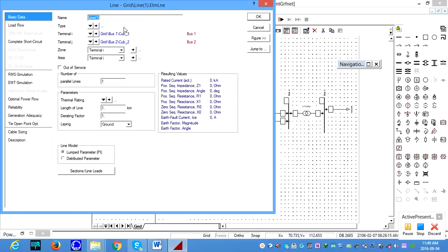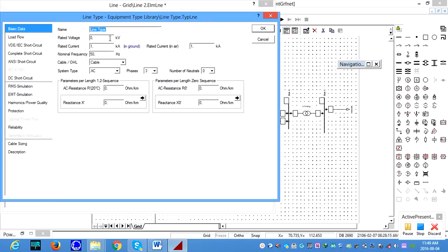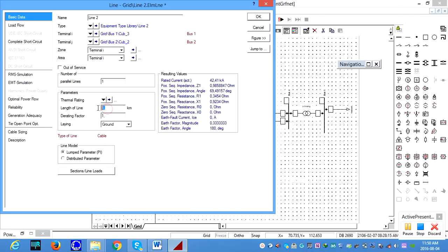And line 2, you can name it as line 2. Okay. And you can go and select a new project. And we can say line 2. And the rated voltage is again 33 kV, and the current is the same because it's a parallel line. The rating of line 1 and line 2 are the same. Okay, and the resistance is like the previous data, 0.3454 ohms per kilometer, and your reactance is going to be 0.9234 ohm per kilometer. Okay. We are happy about that, but the line length is the same as the previous one, 10.12 kilometers.